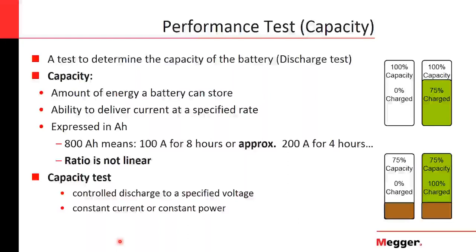It is expressed in ampere hours. For example, an 800 amp hour battery means that the battery can deliver 100 amps for 8 hours. Nominal rating is usually 8 hours. There are some other countries or manufacturers that use 10 hours or 5 hours. The most common here in the US is 8 hours.